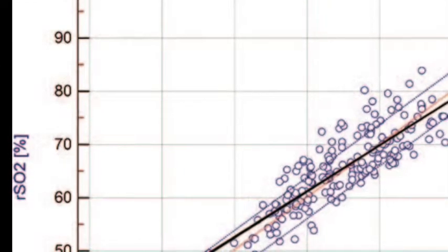Their results are published in this month's issue of Anesthesia and Analgesia and discussed in the article titled Absolute and Trend Accuracy of a New Regional Oximeter in Healthy Volunteers During Controlled Hypoxia. The authors compared regional oximeter results obtained from the left side of the subject's forehead to blood samples taken from the radial artery and internal jugular bulb vein.